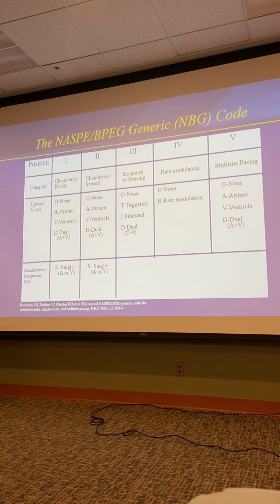It paces in both chambers, it senses in both chambers, and has the ability to both be triggered and inhibited. The second most common one you'll see is DDDR. Same thing as a DDD pacemaker, and we've turned on the ability to be sensitive and aware to how active you are. I think it's extremely unlikely you'll see any of the other configurations. Oh, excuse me, and VVI. That would be someone who has permanent atrial fibrillation. So they only have a ventricular lead-in. And it would be pacing and sensing in the ventricle, V, and then I for inhibited.